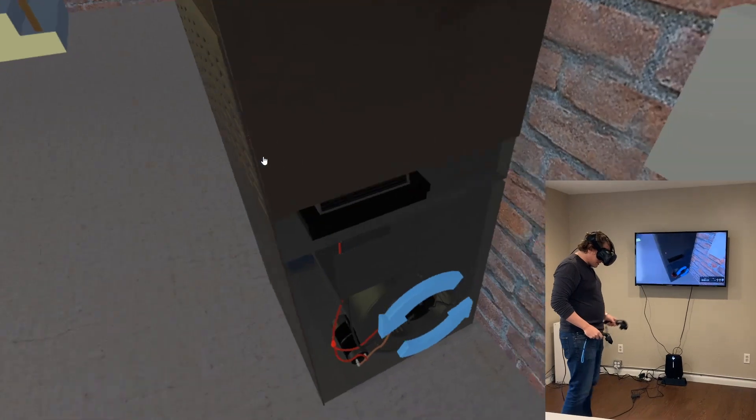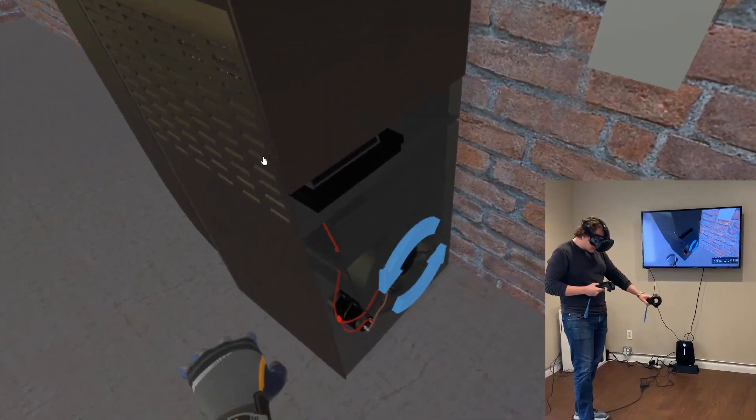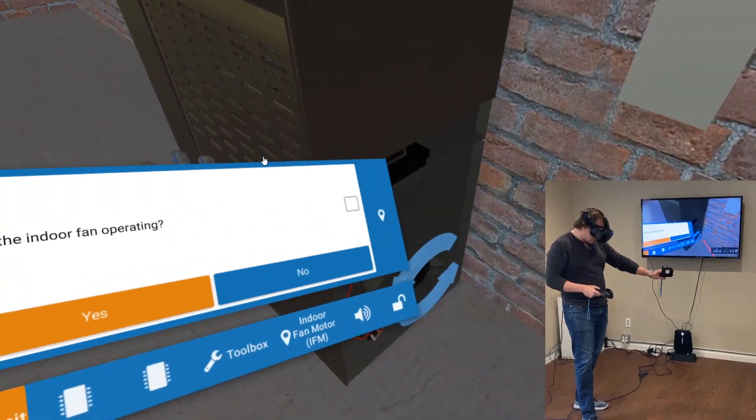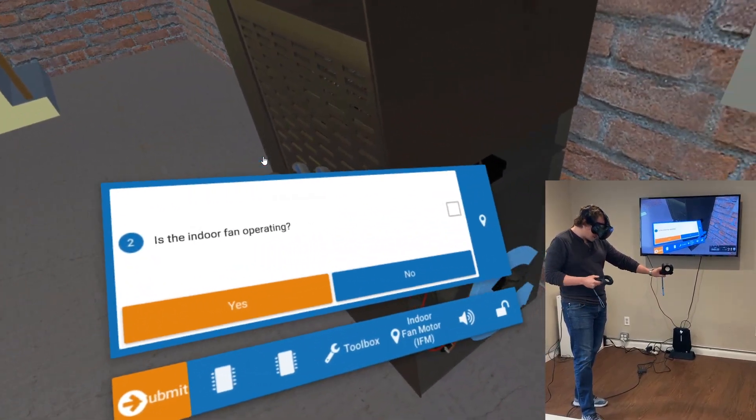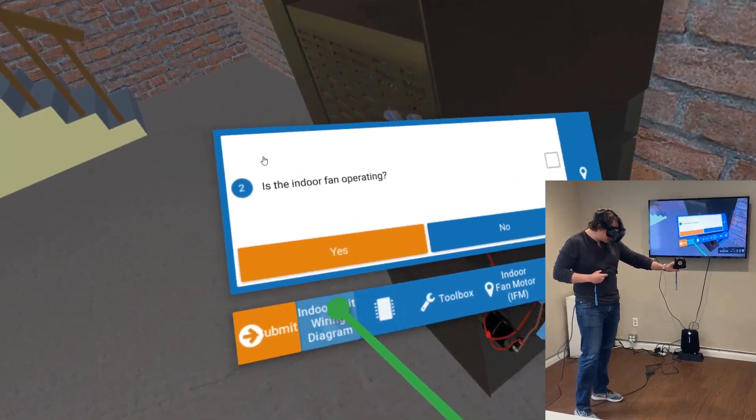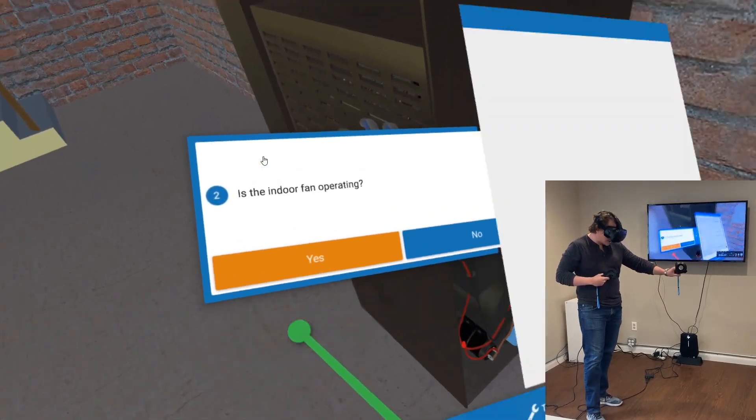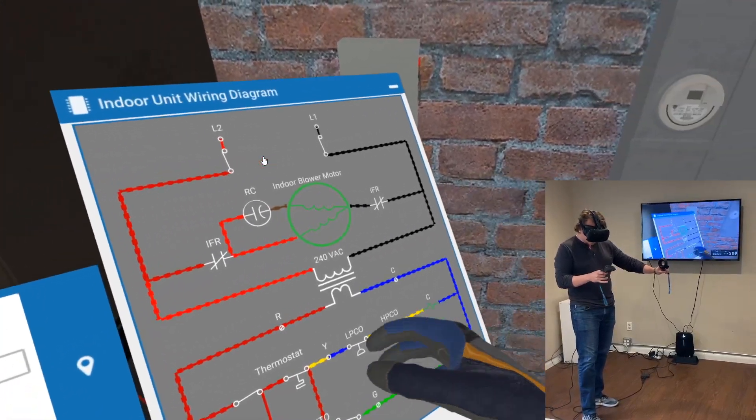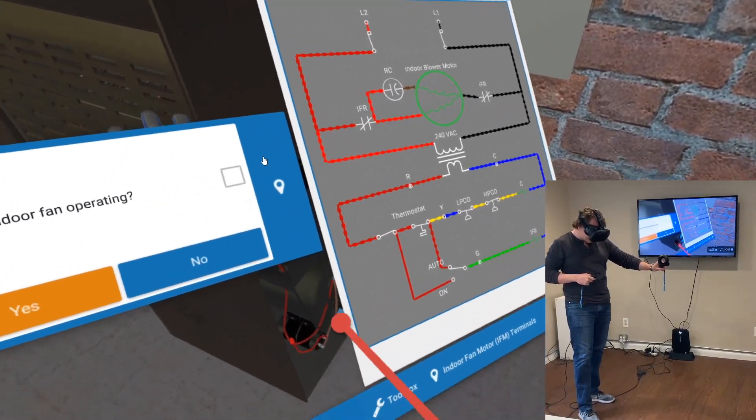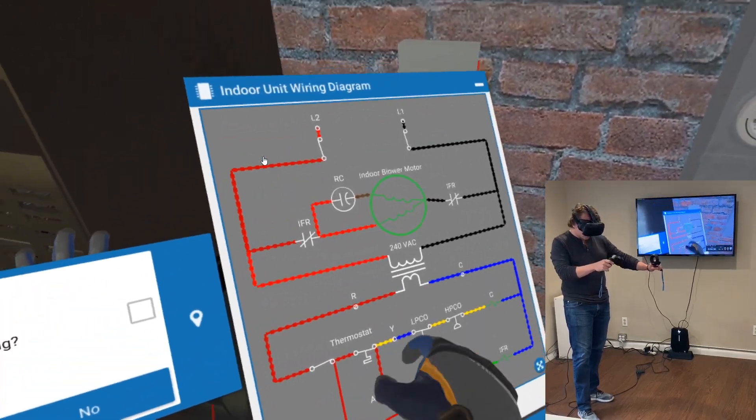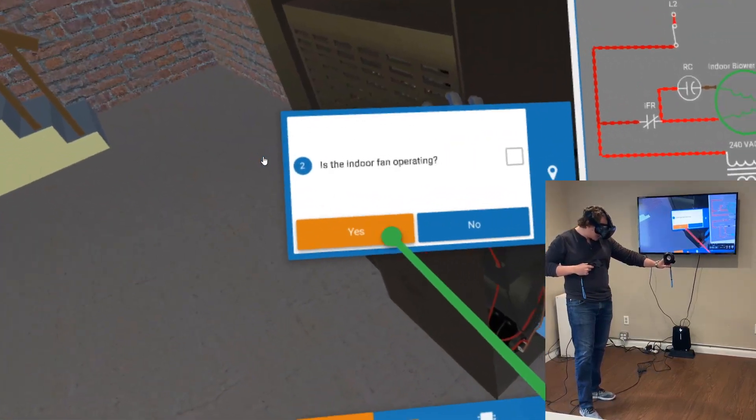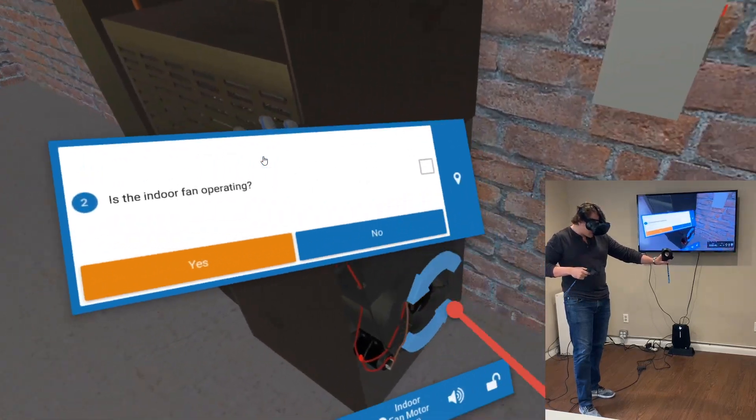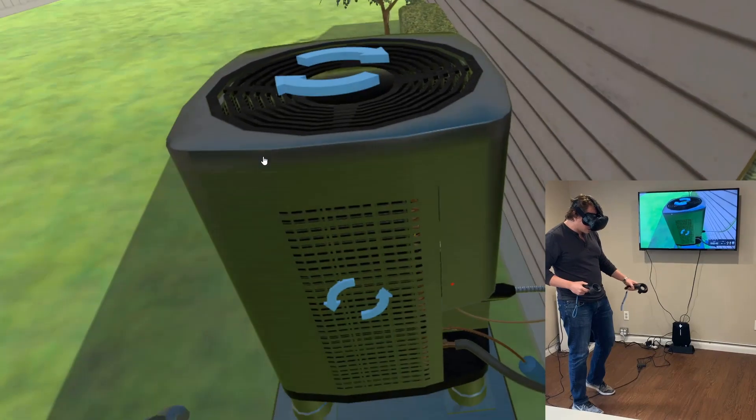The system is operating. Listen for a running motor - okay, we have a running motor, and visually I can see it here as well. Throughout this training, you can bring up your wiring diagram. In this case, we can actually see the indoor electricity running in this indoor unit, so I'm pretty confident that the indoor fan unit is running.